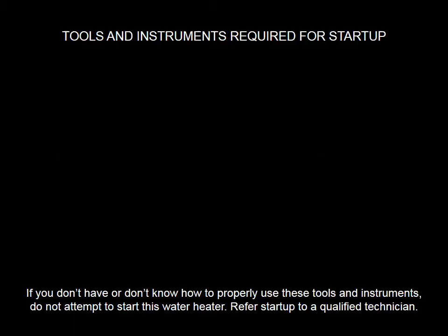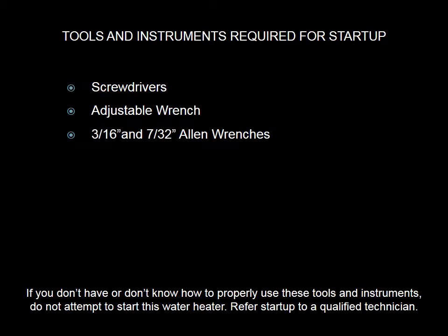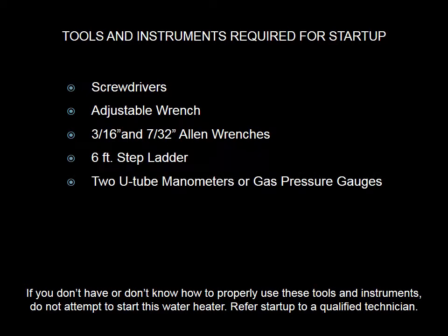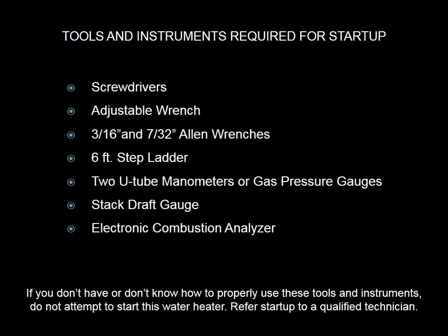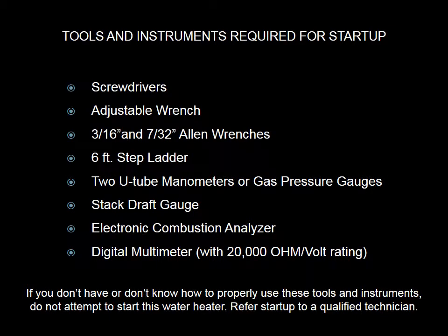The following tools and instruments are required to start up the CONQUEST water heater. You will need flat and Phillips head screwdrivers, an adjustable wrench, 3/16 inch and 7/32 inch Allen wrenches, a 6-foot step ladder, 2 manometers or pressure gauges that are capable of reading both positive and negative pressure, a stack draft gauge, an electronic combustion analyzer, and a digital multimeter. If you don't have or don't know how to properly use these tools and instruments, do not attempt to start the water heater. Refer startup to a qualified technician.